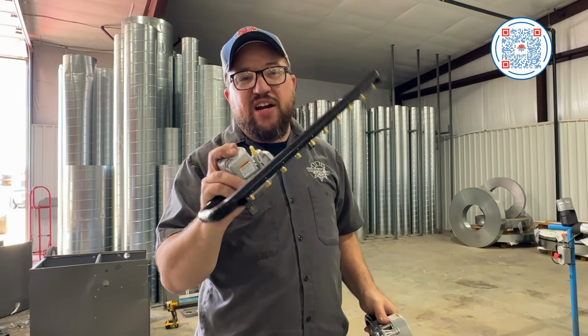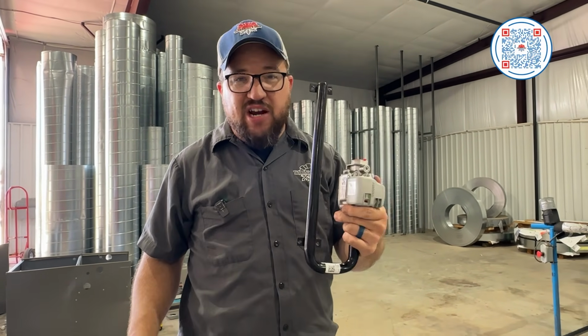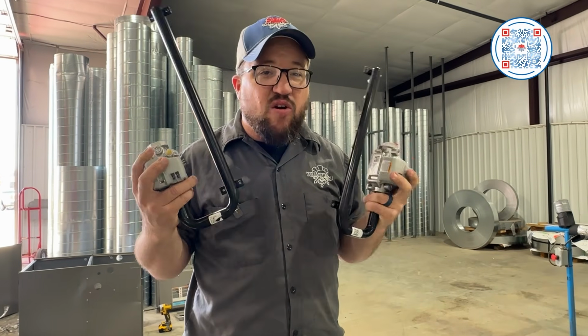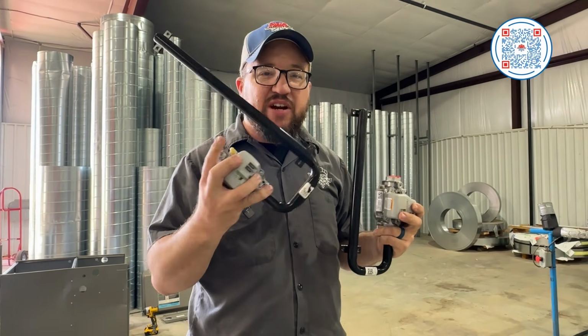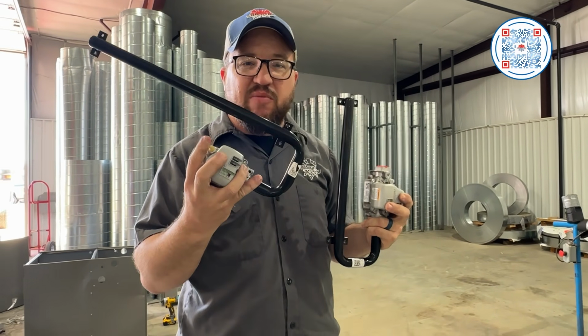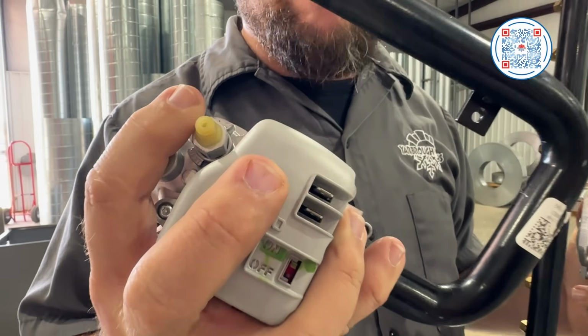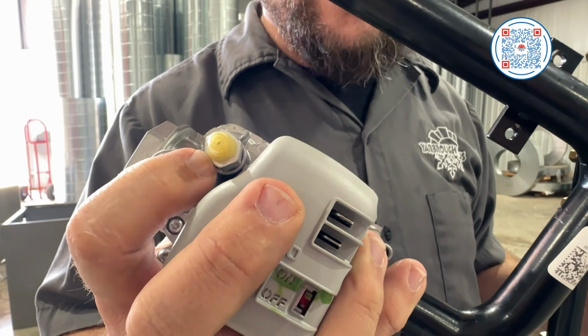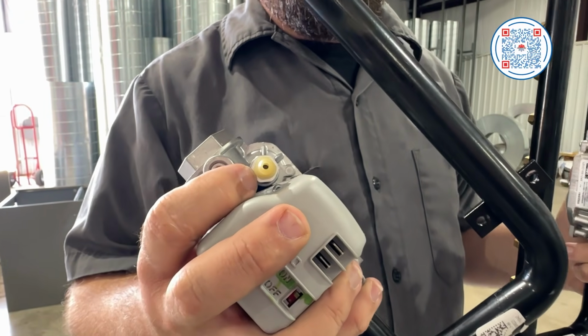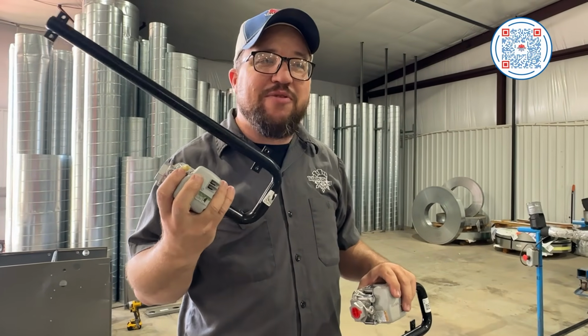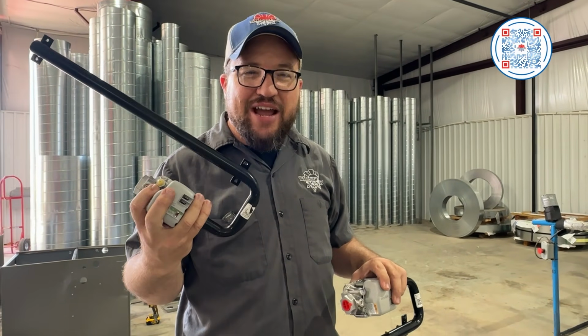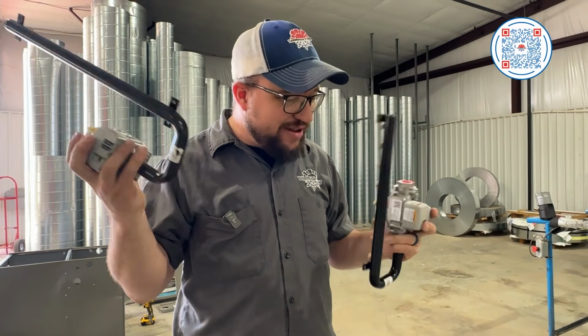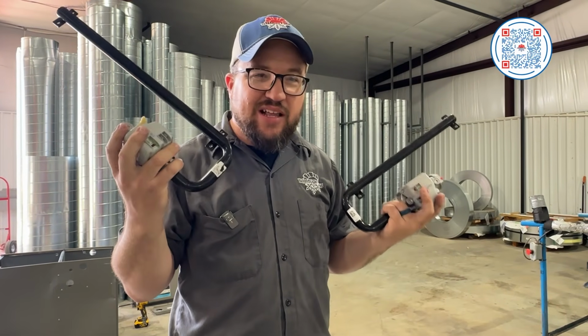This one is your 90%, and this one's your 80%. Needless to say, they are almost identical, minus this one has another port where it's reading pressure in the actual cabinet to judge how much gas it wants to give. That is a big difference, makes it a little bit more of a pain whenever we got to check them for gas pressures and all that good stuff. But overall, both of these, I like them.